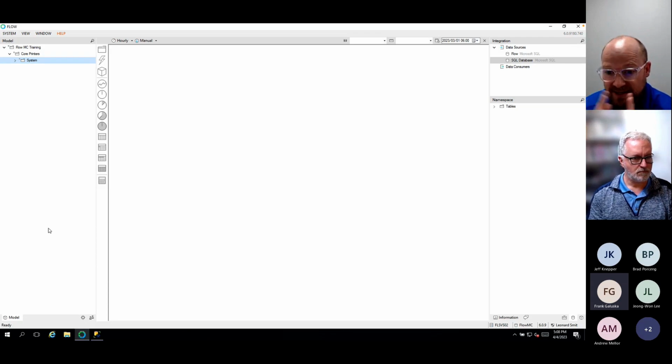We do aggregate data into time buckets: minutes, hours, days, shifts, whatever the case is. But what if you want to do some pre-cleansing of that data before you go into that aggregate? I want to remove outliers. I want to potentially remove negative values from my flow transmitter. I want to potentially apply a rule to say, only look at this value when I'm in a certain state. And that state can come from a completely different data source.